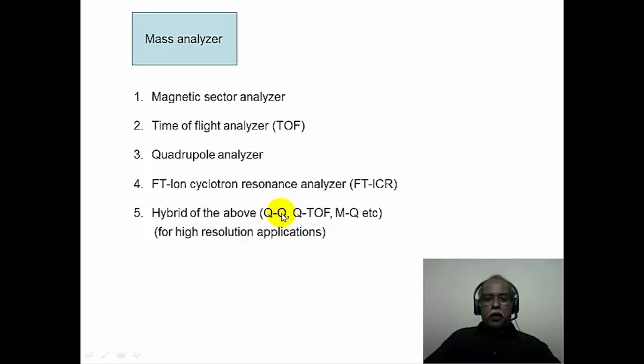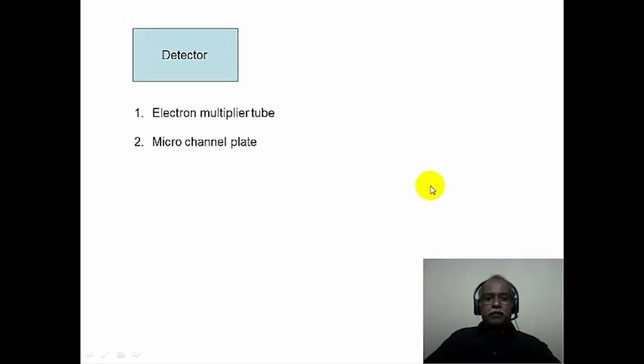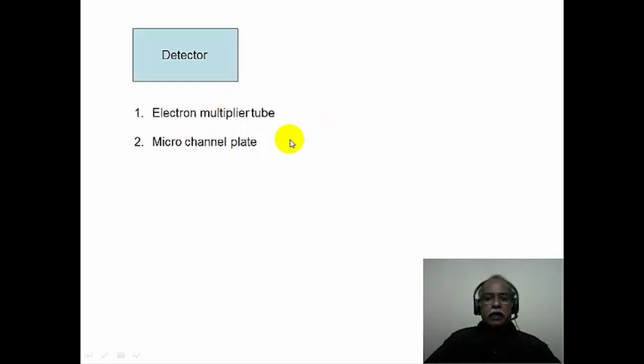For example, one can have a quadrupole-quadrupole, triple quadrupole, or quadrupole time-of-flight analyzer. Such combinations are generally used when high resolution is necessary. The detectors used are essentially electron multiplier tubes or micro-channel plates. Ions impinge on the electron multiplier tube, producing a current that is registered as a signal corresponding to the recorded mass spectrum.